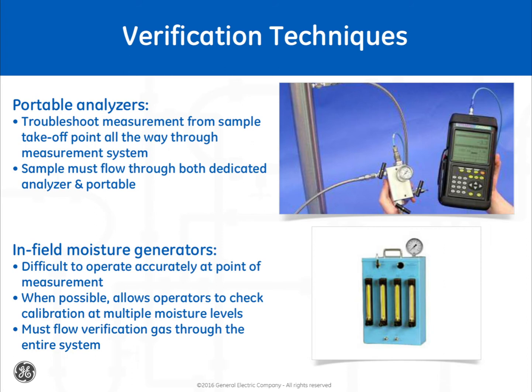Some prefer to use a moisture generator in the field to check their analyzers. Most moisture generation techniques are difficult to operate accurately at the point of measurement. In cases where this is possible, and these verification gases pass through the sample system and then pass the sensor, this method allows the operator to check the sensor's calibration at multiple moisture levels. It may be difficult to generate these moisture contents in the same background gas as the application or at the same pressure as the application.